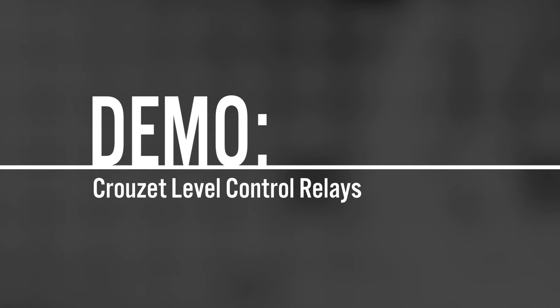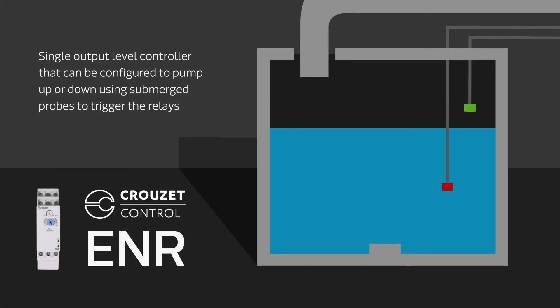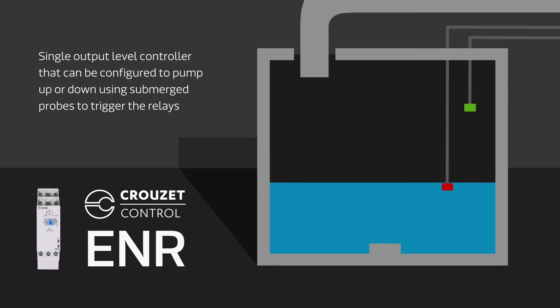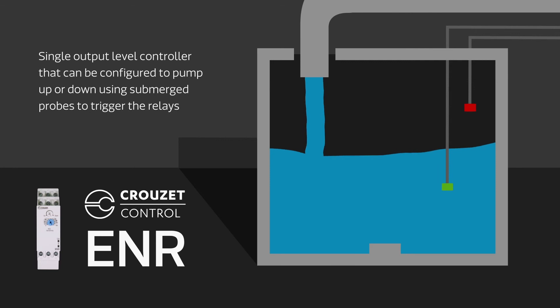Crouzet's ENR is a single output level controller that can be configured to pump up or down and relies on submerged probes. The pumping action and sensitivity is set from the front of the unit. For filling or pumping up, the relay turns on to start the pump once the liquid drops below the bottom probe. For emptying, it turns on when the liquid level reaches the top probe.